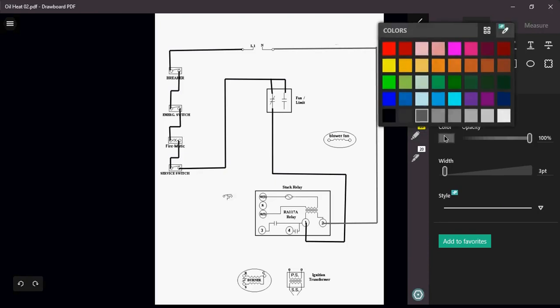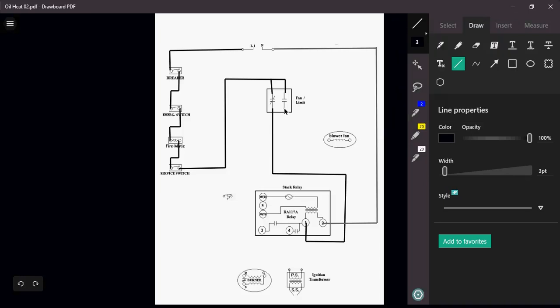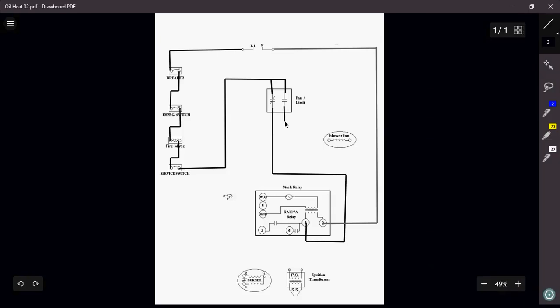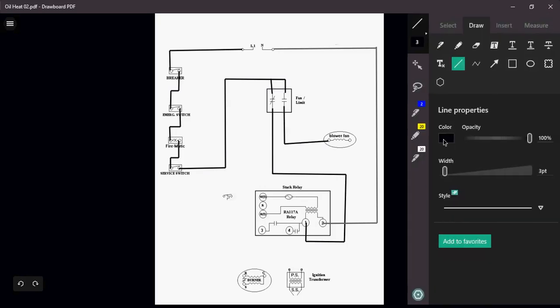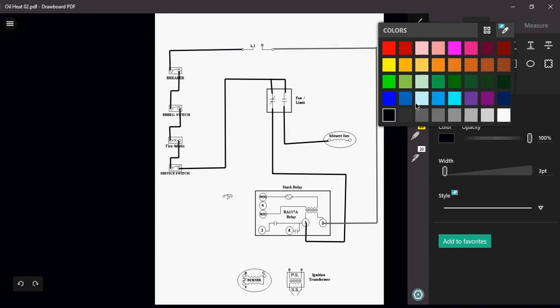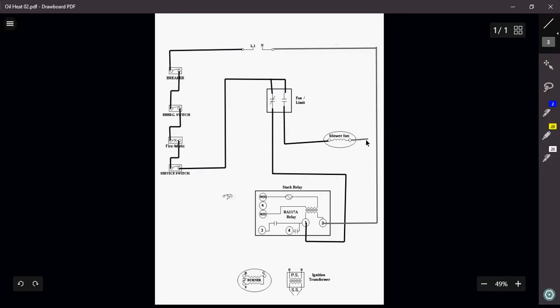So now I want to do my other side of my fan limit switch. I'm going to do my fan side. Now remember, this guy is going to close at approximately maybe about 140, maybe 150 degrees, somewhere in there. This guy is going to close. And when that happens, my blower is now going to come on so that I can start delivering heat to my space.